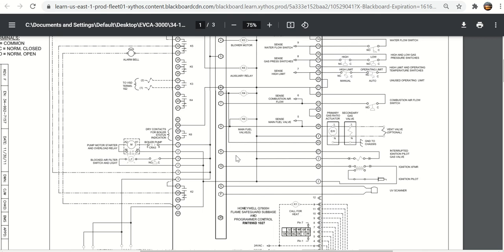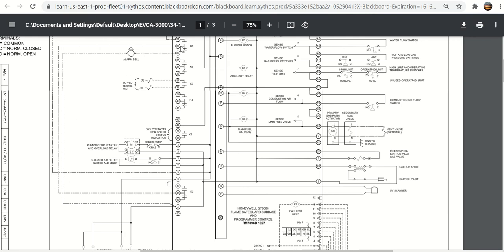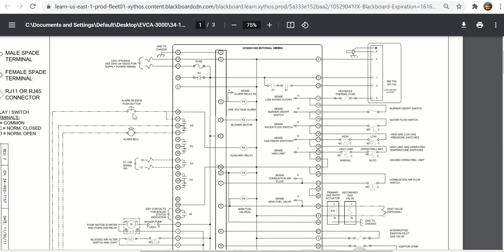When you scroll down here, you'll see here is the switching side of K2. Right here is the coil. When the relay energizes, there's the coil for it. Here is the actual switching common, normally open terminal, normally closed terminal. Power comes in here, comes through the normally open terminal. When K2 energizes, this contact closes, that one opens. Power comes up here, goes over to terminal number 32 of K5. If the K5 relay is not energized, power goes to the alarm bell. And then the other side of the alarm bell goes back to terminal number two, which is your neutral. So the alarm bell rings.